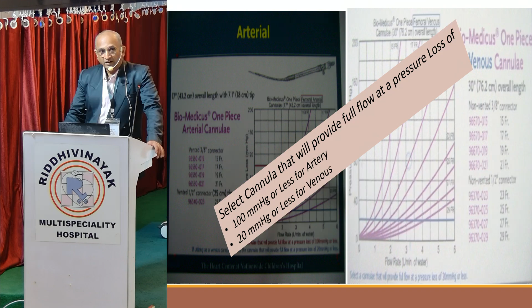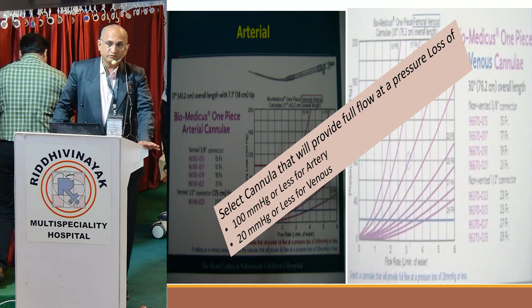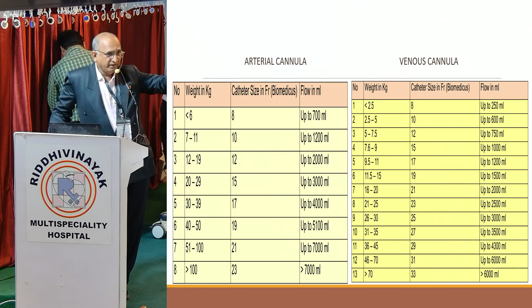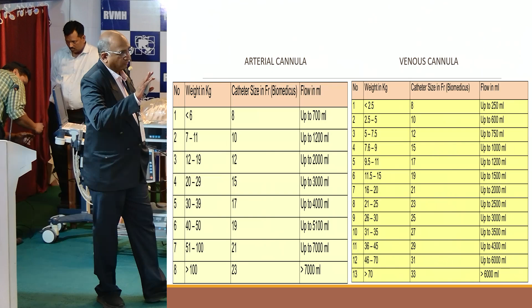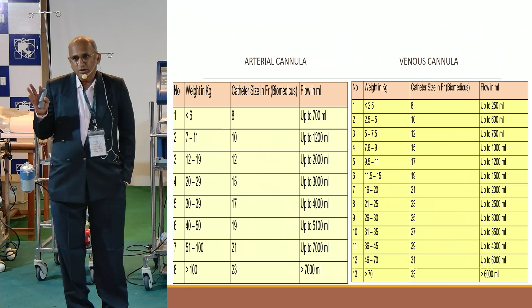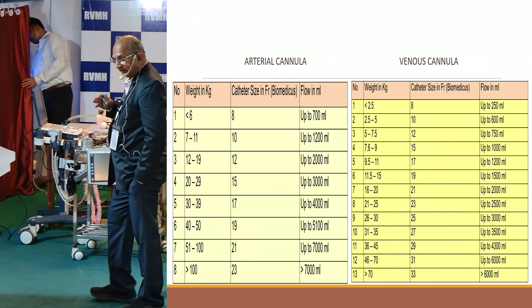So select the cannulas that will provide you full flow at a pressure loss of 100 mm of Hg for a return cannula and 20 mm of Hg for a venous or drainage cannula. So depending upon that, you can select the size. I just simplified it from the graph to numbers, so that you know with what weight of the patient, how much flow will be required and what size of cannula you use. In adults, usually you use 25, 27 or 29 French for drainage and 19 or 21 for a return cannula.